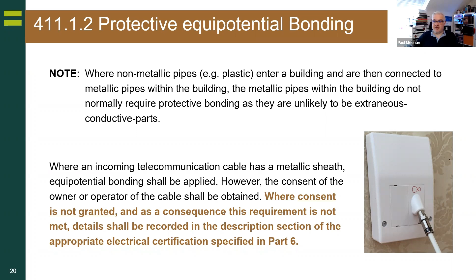One of the other things I have to give you a warning and careful consideration on: MLCP, it's a plastic pipe, the plumbers love it, but inside it's got a conductive aluminium core to protect it. Well, if that's not installed correctly, then surely that pipe, even though it appears plastic, could potentially still be conductive. I only found this out from a plumber who came to my house recently, and it was a really interesting thought piece. So just be mindful, if it's plastic, if it's got a core, has it been connected correctly?